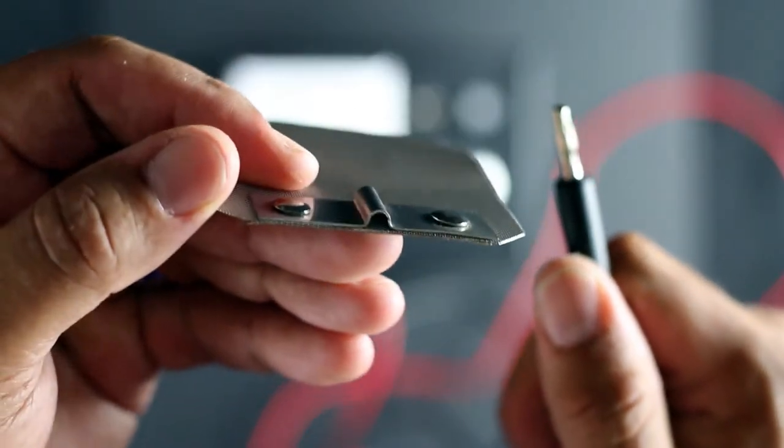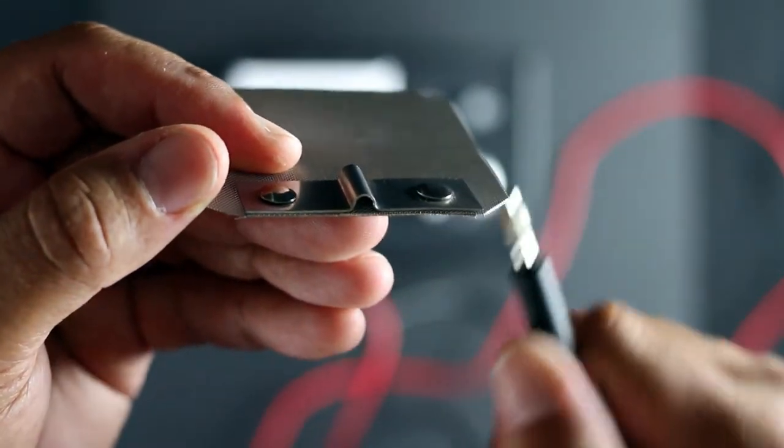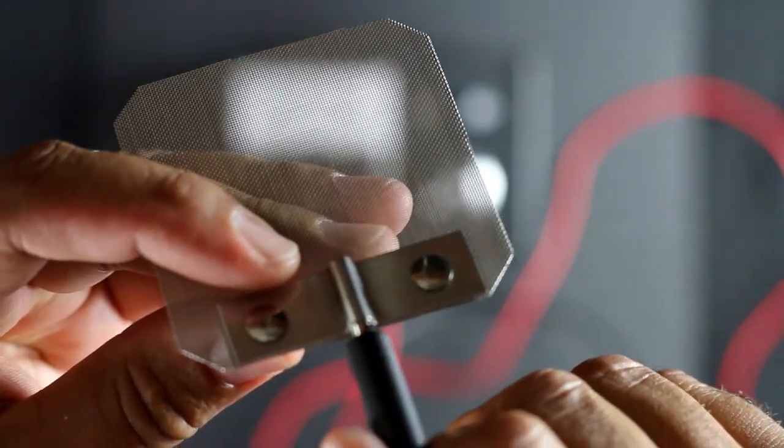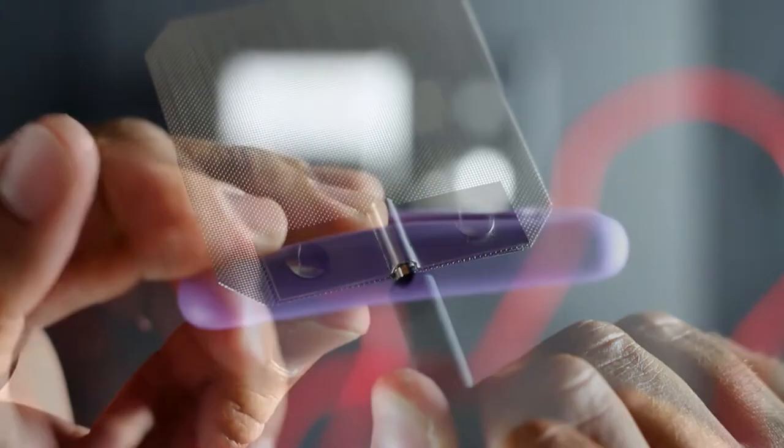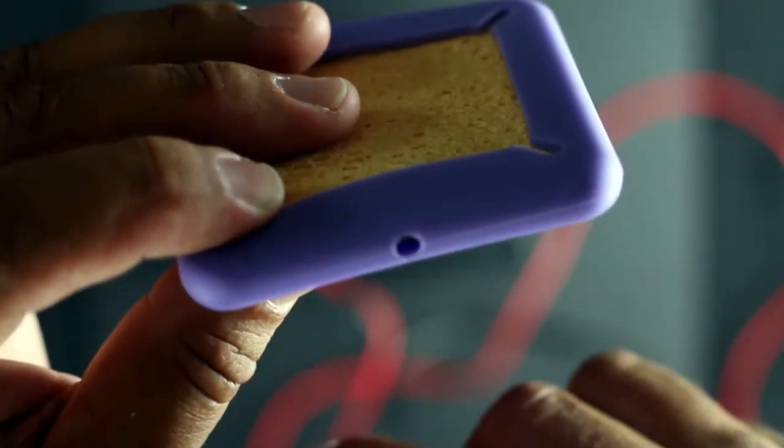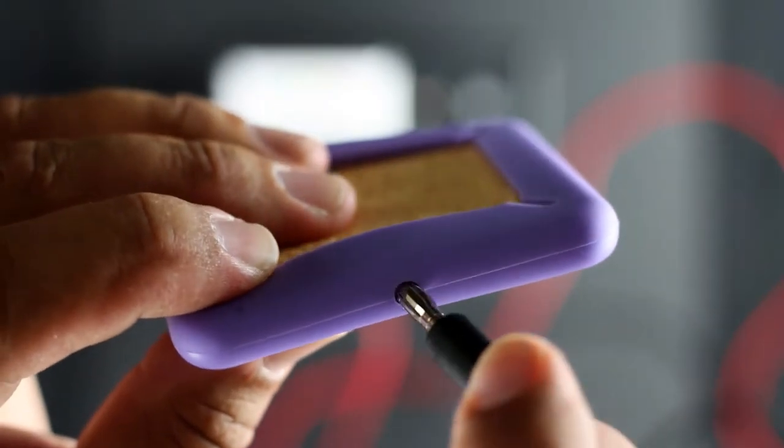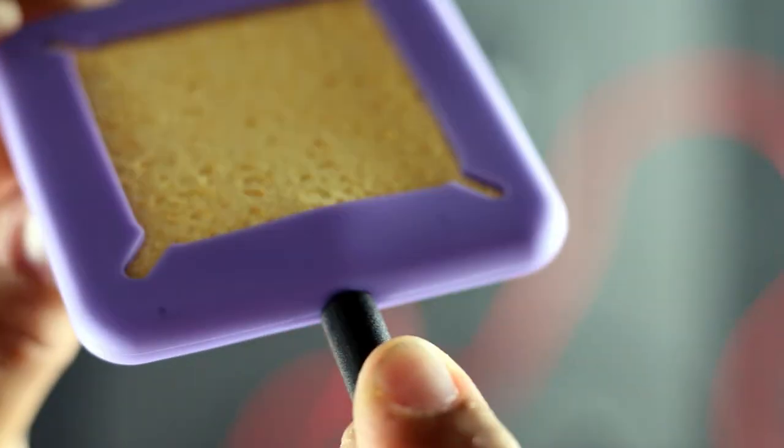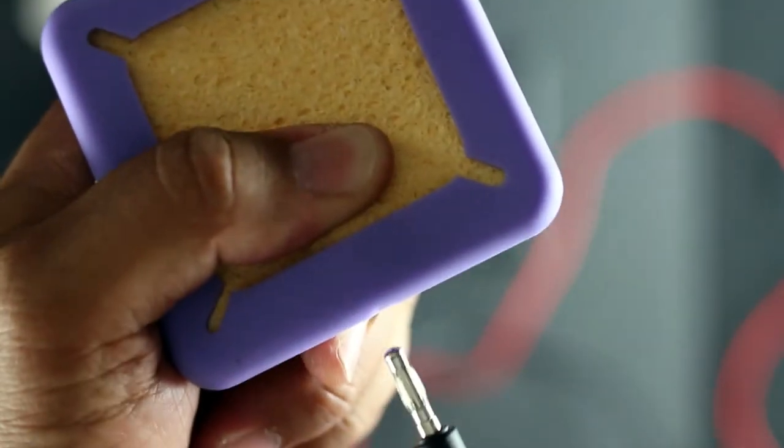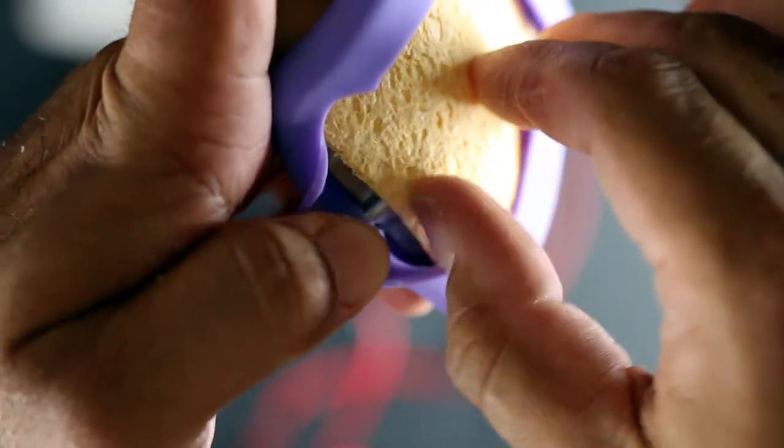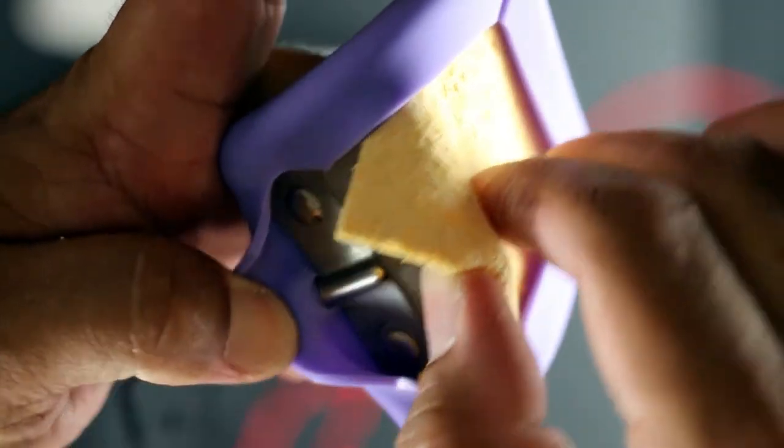What you have inside the electrosquare electrode are these custom made plates. And what you're doing when you're inserting the cable is you're inserting the banana plug right inside this loop. So what you want to do is ensure that the electrode corresponding plate is centered accordingly. Usually all that's required is for you to insert it and put it in. If you want to make sure that the plate is inserted on metal, you could open the electrode and inspect it to be sure.